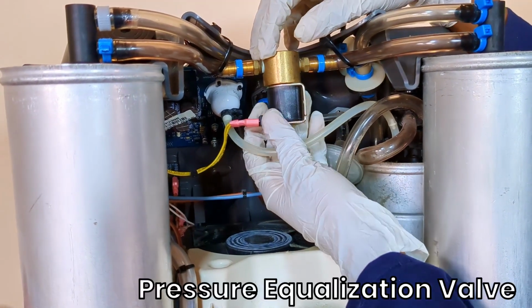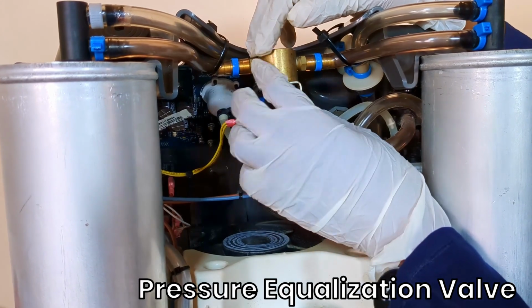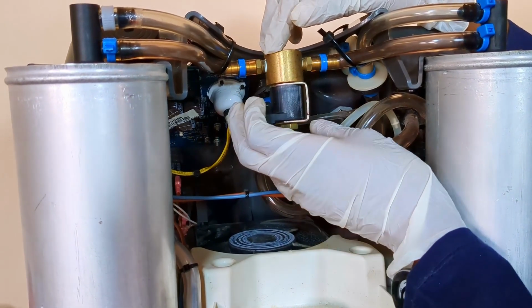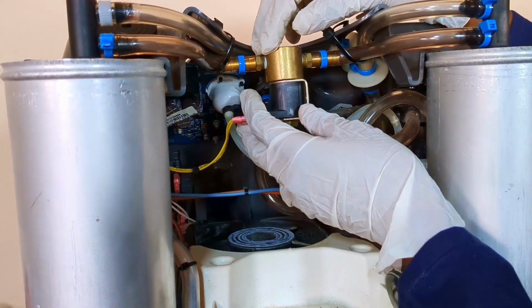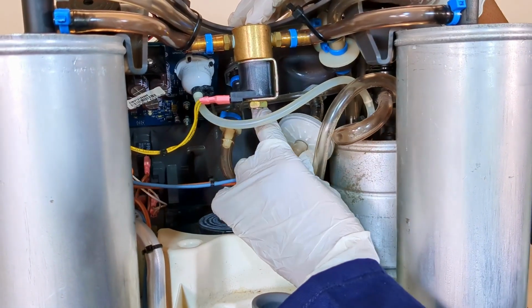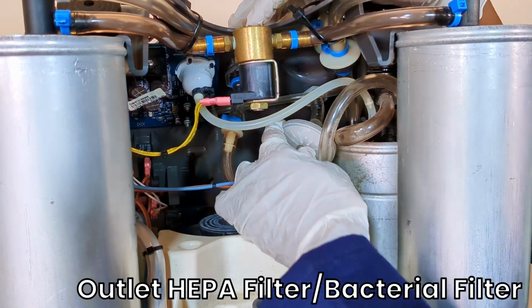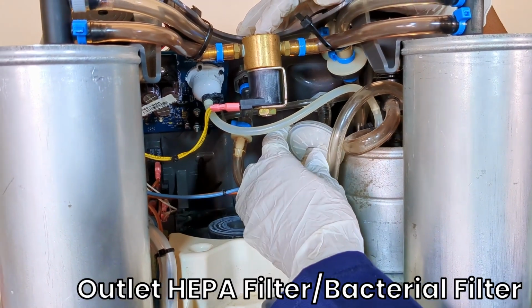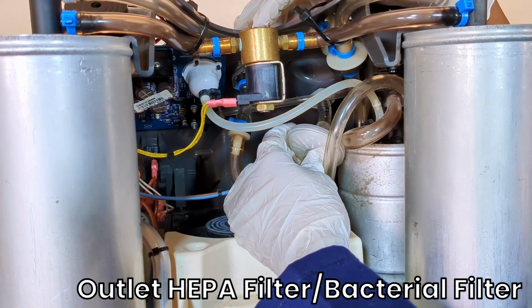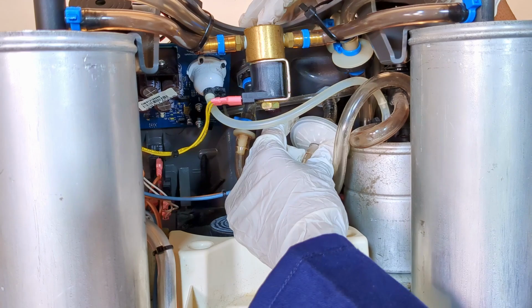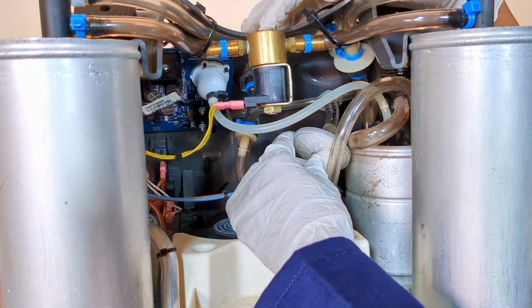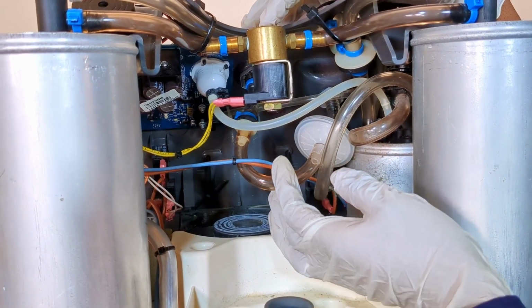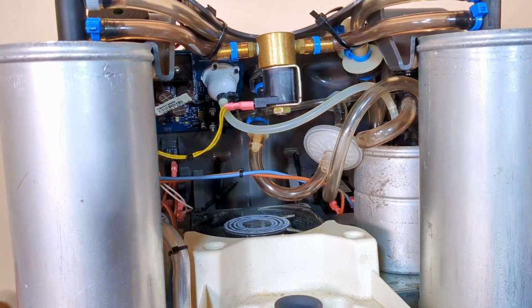This is the equalization valve. This valve allows part of the pressurized oxygen to enter the depressurized sieve bed. Here we have the outlet HEPA filter, also known as the bacterial filter. This filter is used to remove contaminants from the concentrated oxygen prior to delivery to the patient.